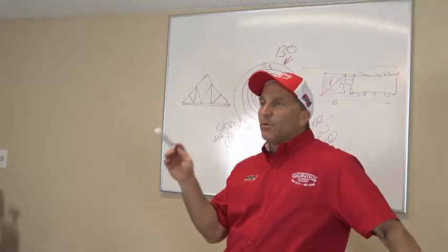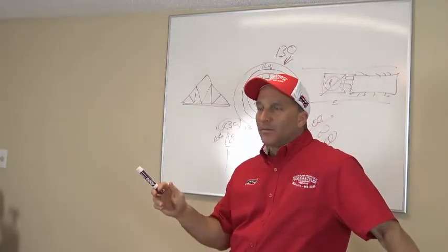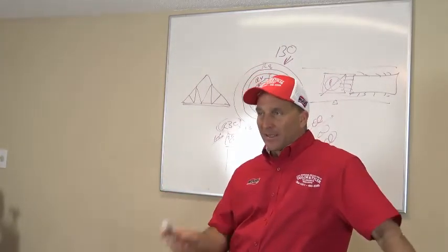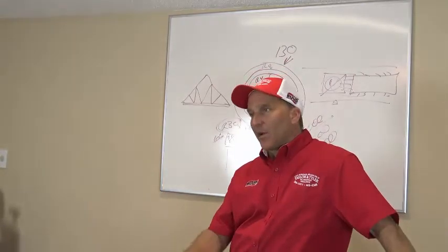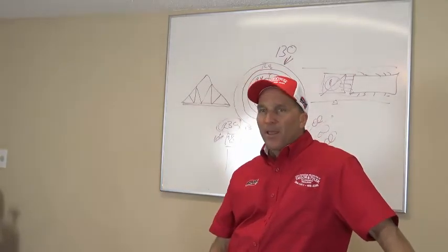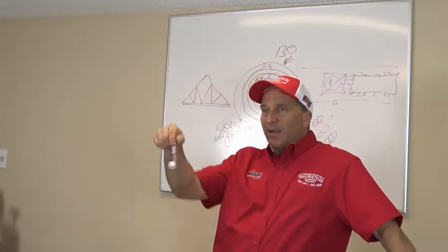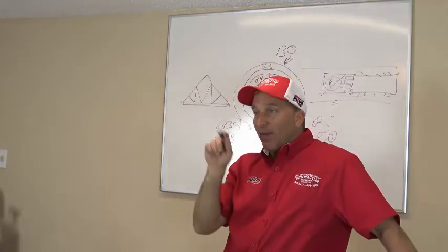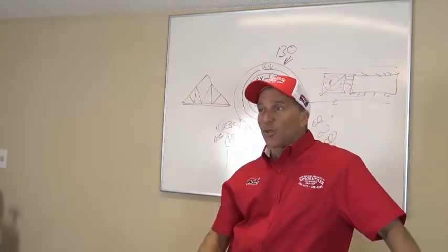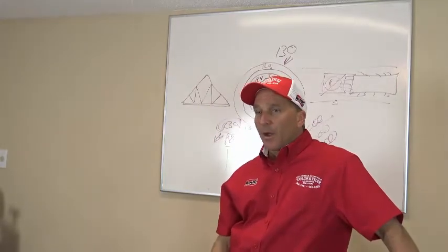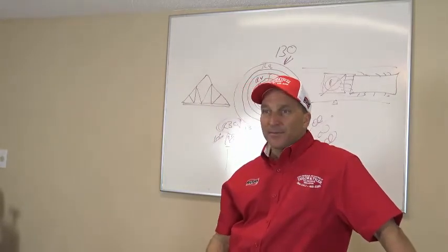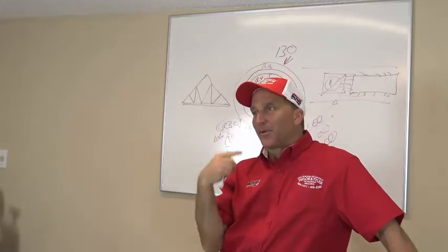So that fuse, that breaker should not trip, right? He goes, "I agree with that." I said, "I'm going to tell you what's going to happen, because I already checked it was grounded, okay? When I put the fuse back in, this fan motor is going to run. And if that fan motor runs, that means he did the correct job." "All right." I said, "Okay." So put the fuse back in, fan motor runs.